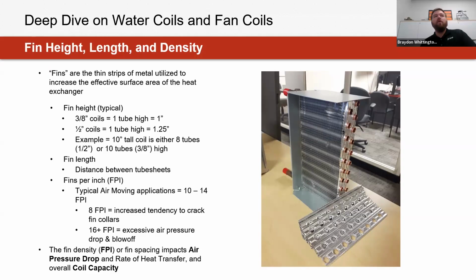Good question. In terms of the coils itself, that's actually the tubes that are passing through it. Those connections, though, are what are actually varying. These are not the end connections of the coil. It's more so the tubes that are actually passing through the fins. You are dropping internally, there's a reducer at the coil connection, and you're actually running 3/8 inch tubes through some of these coils. Right. I did not know that.